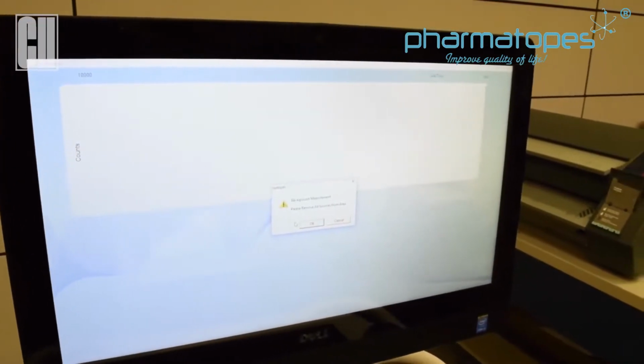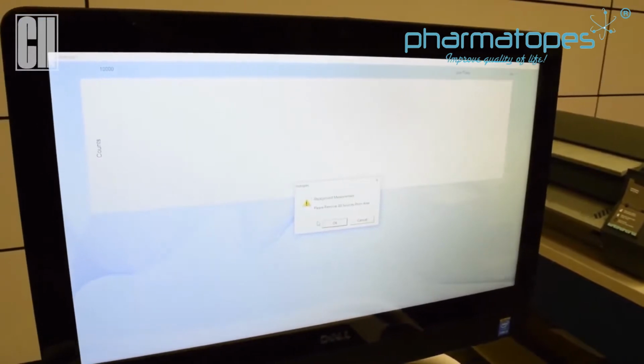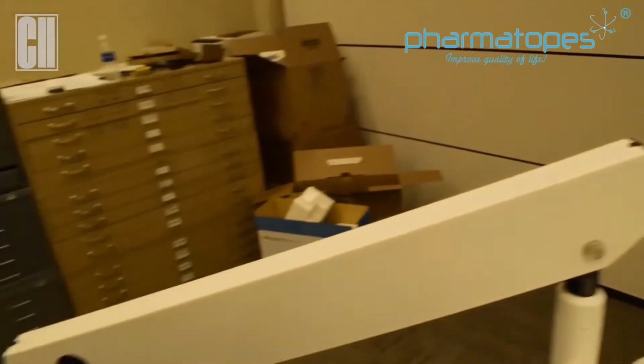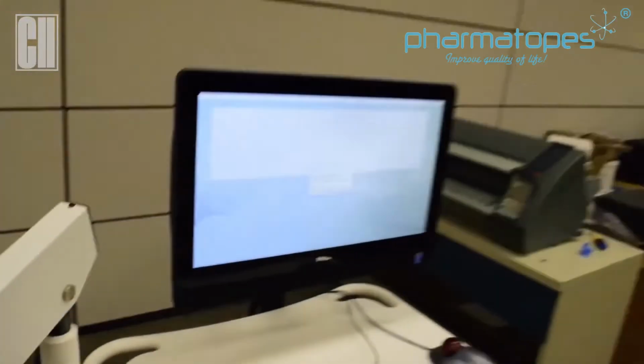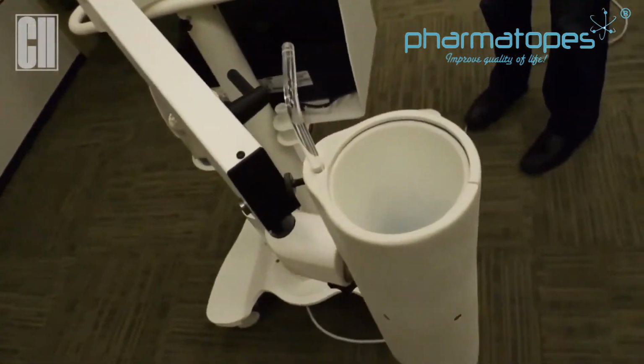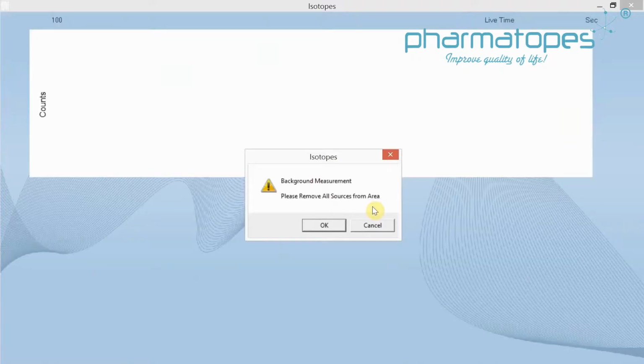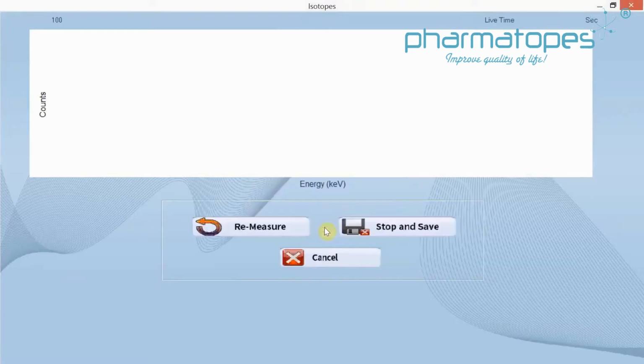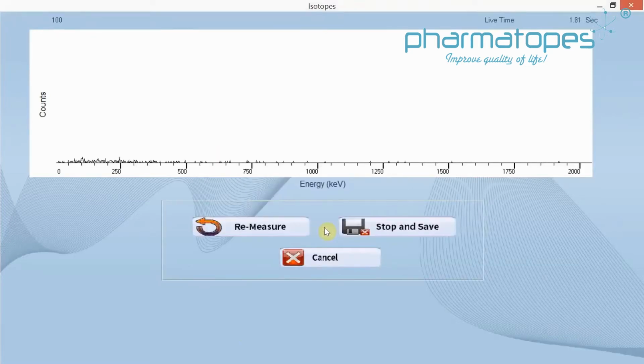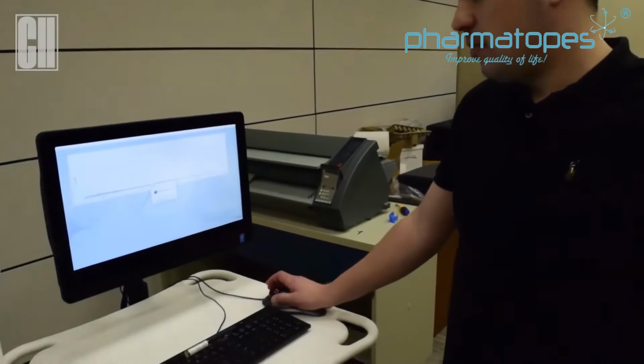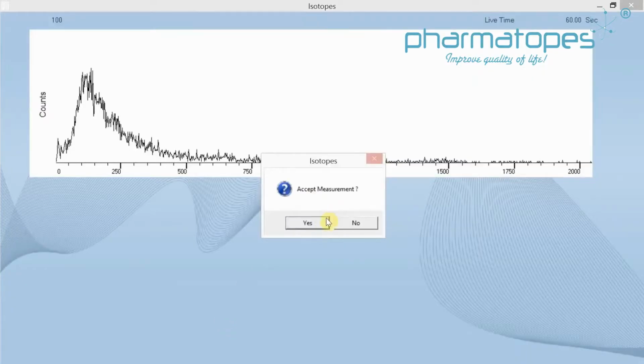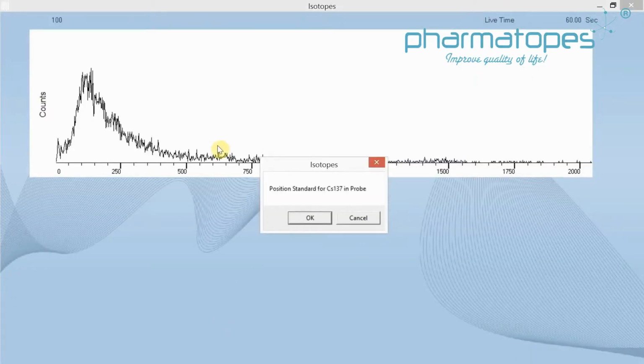So we want to make sure that all the sources are removed from the probe. Once you verify the sources are removed from the probe, you click on OK, and we'll count the background for 1 minute on the probe. The background is completed. We're going to accept the background measurement and position the cesium in the probe.